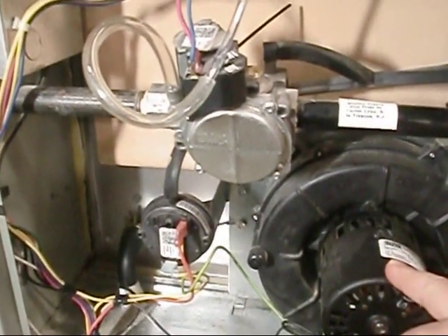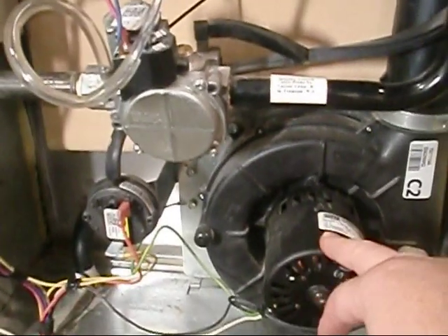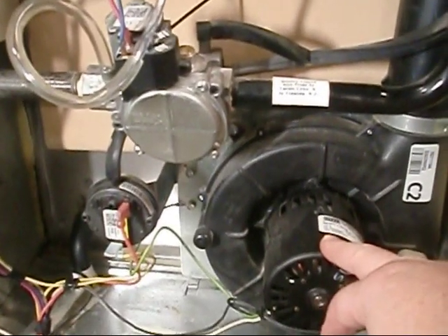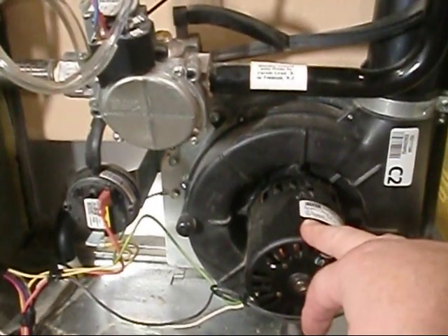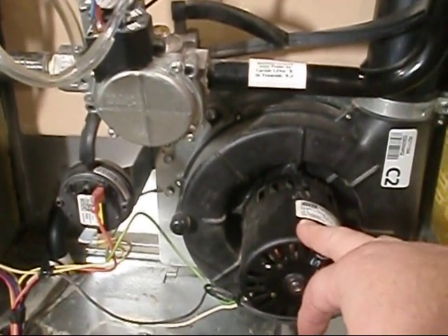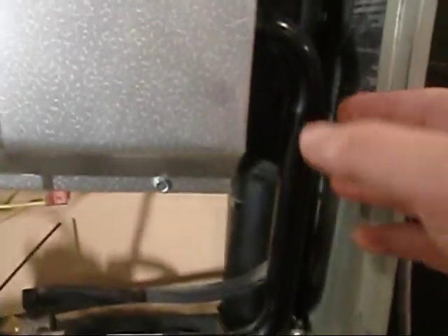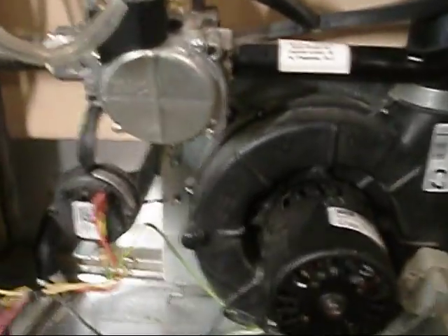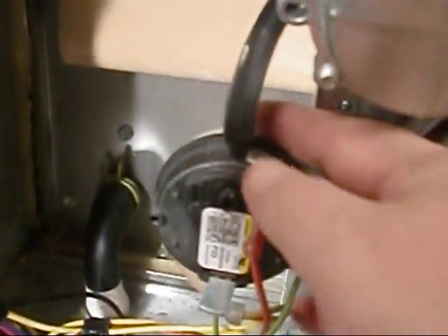It's one of the sequences of operations to get your furnace to fire here, and starts right here with this inducer motor. This inducer motor actually performs two jobs in itself. It supplies combustion air to your burner box, and most of all, it's to get rid of all your CO there.